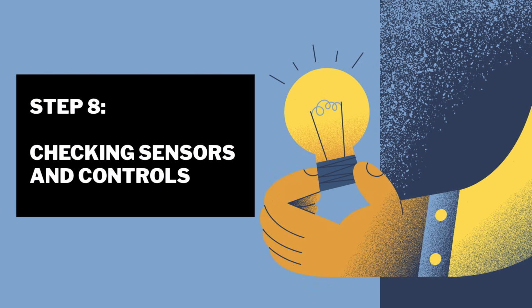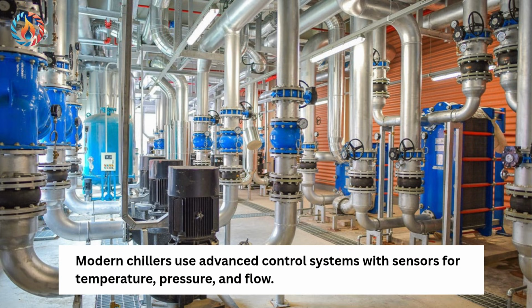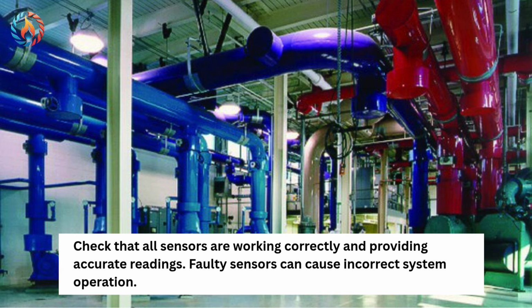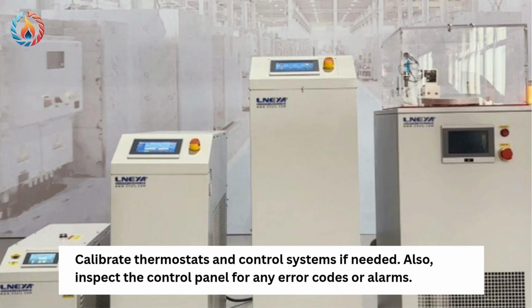Step 8. Checking sensors and controls. Modern chillers use advanced control systems with sensors for temperature, pressure, and flow. Check that all sensors are working correctly and providing accurate readings. Faulty sensors can cause incorrect system operation. Calibrate thermostats and control systems if needed. Also, inspect the control panel for any error codes or alarms.